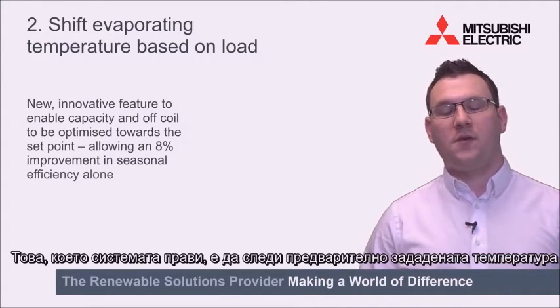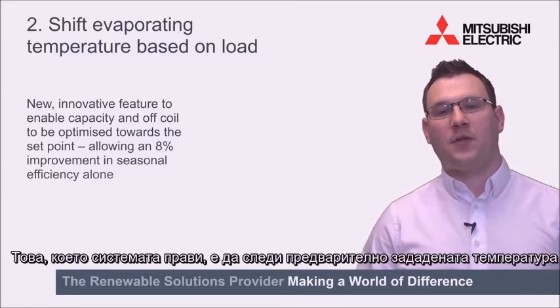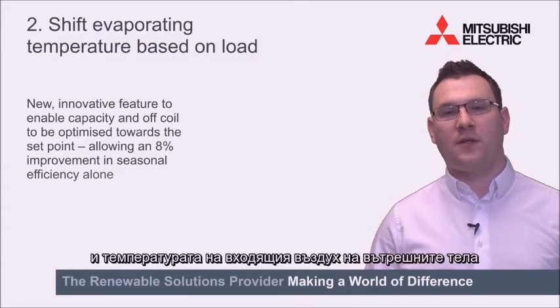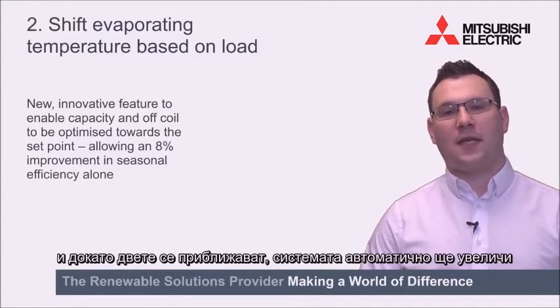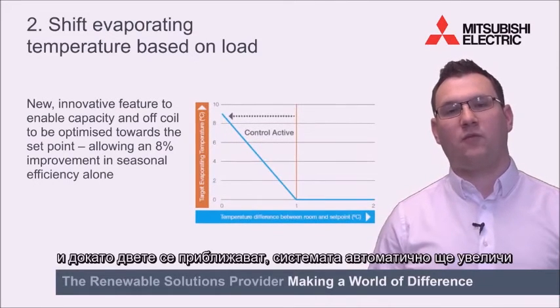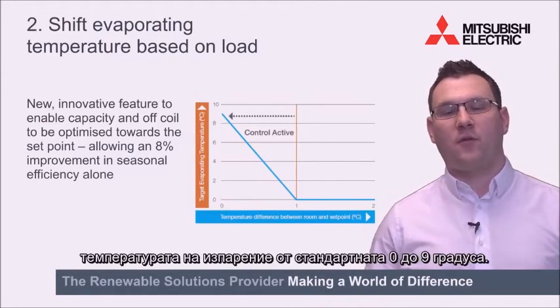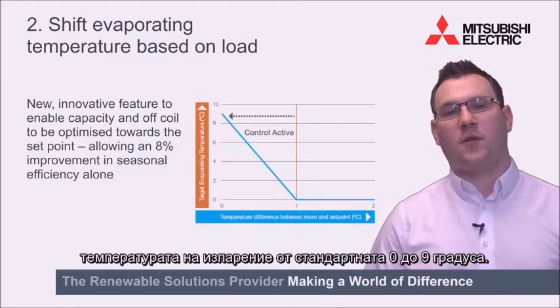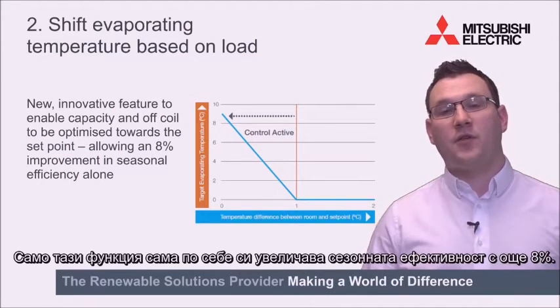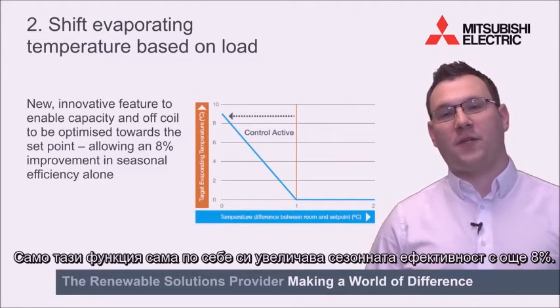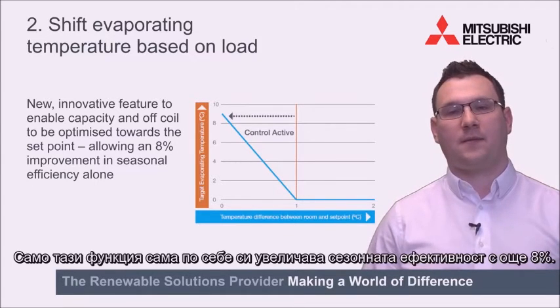What the system will do is it will monitor the set temperature and the inlet air temperature of the indoor units, and as the two get closer together, the system will automatically raise the evaporating temperature from a standard 0 up to 9 degrees. This function alone will increase the seasonal efficiency by an additional 8%.